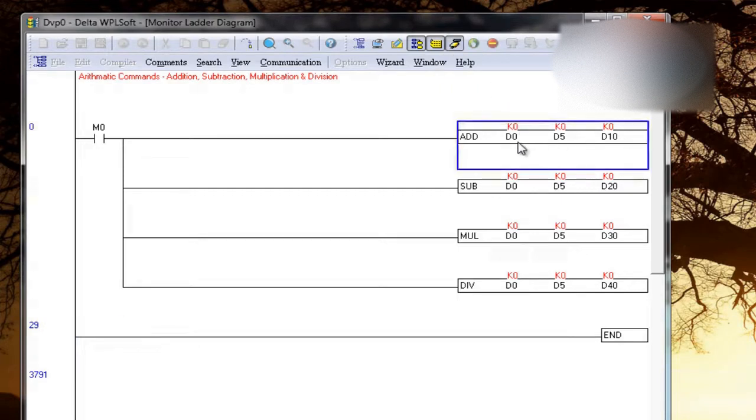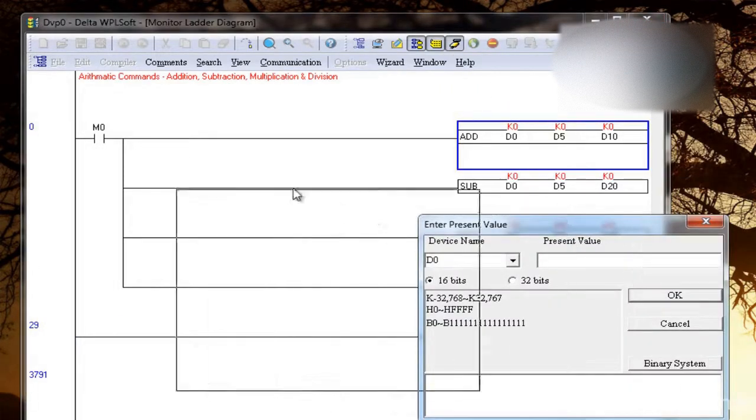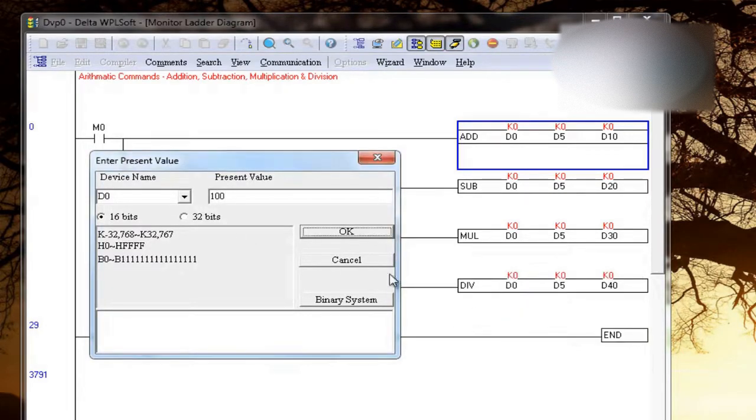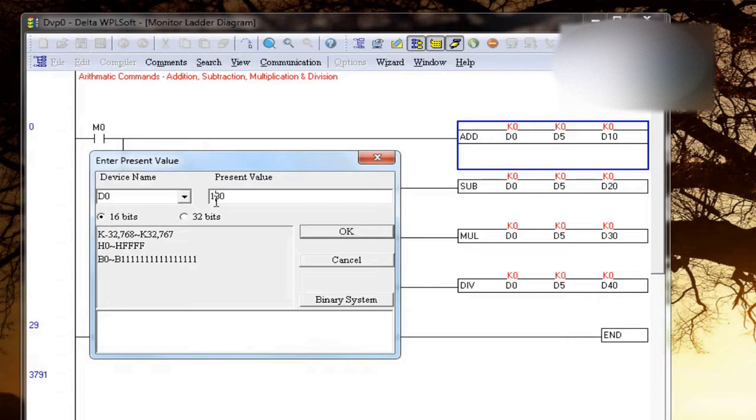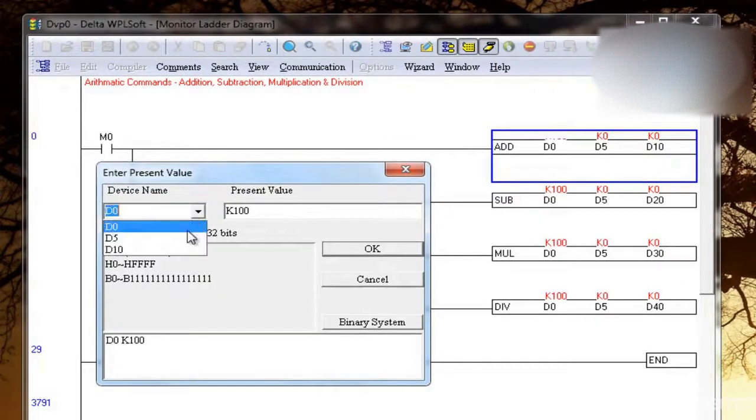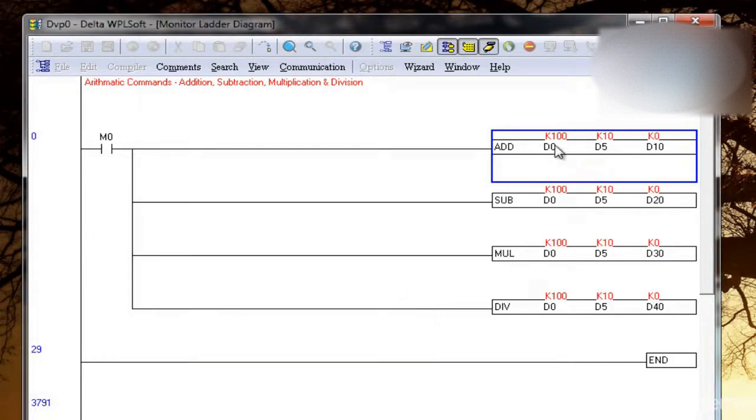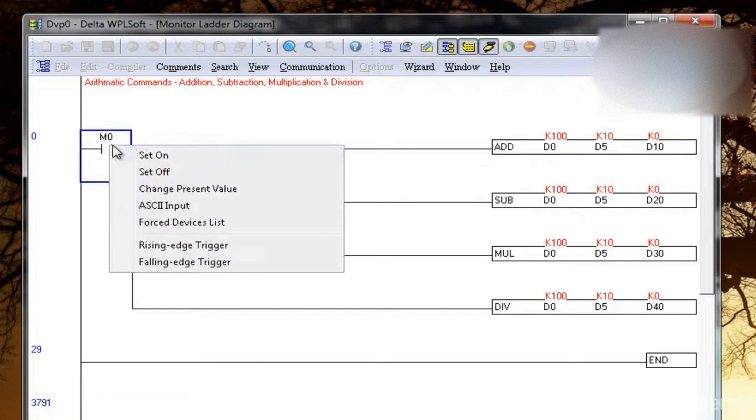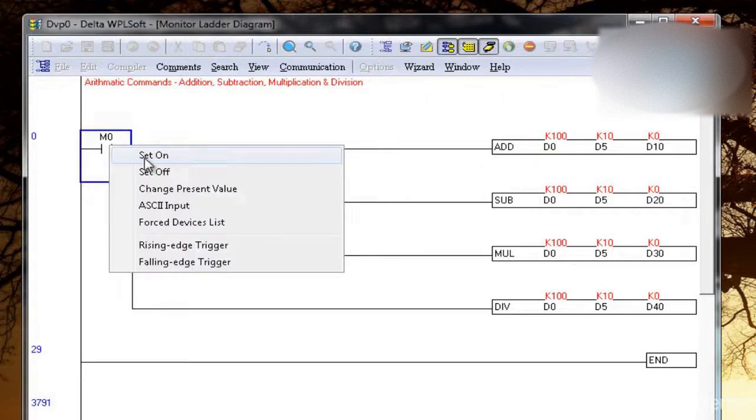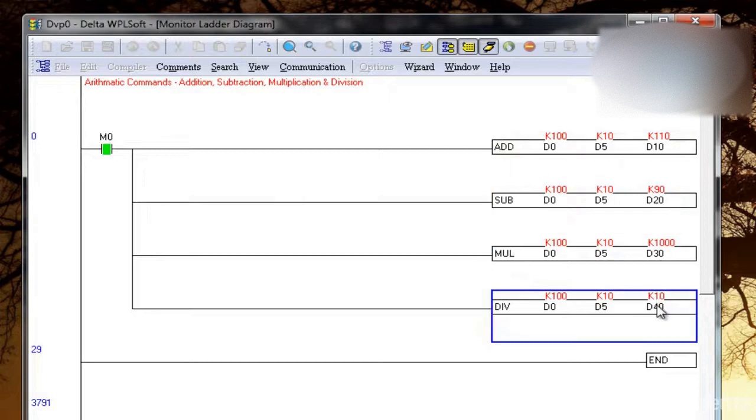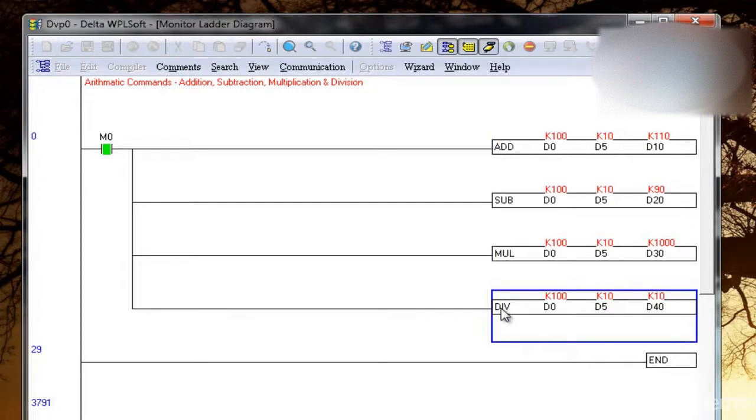So D0, D5 is 0 initially, I will change the value. D0 I am taking, let's take as 100. Sorry, I need to use K here. So this is 100 and in D5 let me take 10. So I know that 100 addition of 10 will be 110, 100 minus 10 will be 90, this will be 1000 and this will be 10. So this will be quickly executed as soon as I turn on M0. So this is 110, 90, 1000, and 10. So this is how you can use arithmetic commands in the PLC by using this syntax: add, subtraction, multiplication, division.